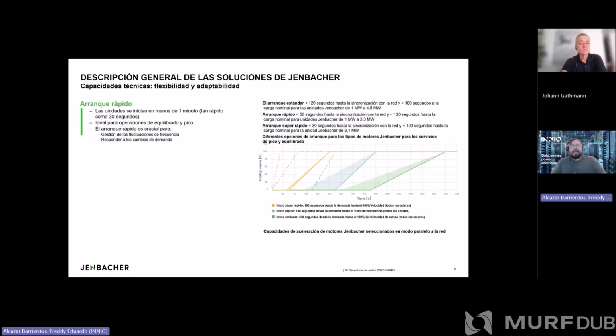First is the quick start part. Our units normally have a synchronization time of less than 1 minute and can achieve synchronization times of only 30 seconds. It should be noted that this is not for all units. Certain models may have this capability, but this ability to synchronize from the start signal to grid synchronization in 30 seconds can be extremely helpful, especially when looking to provide frequency control services.